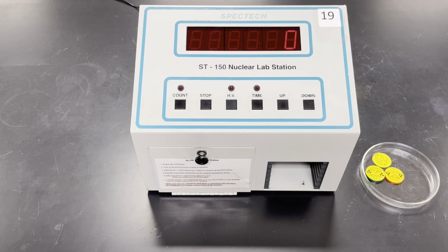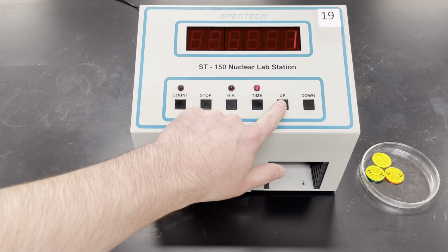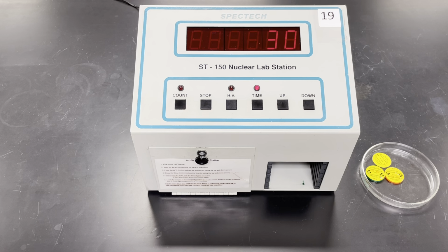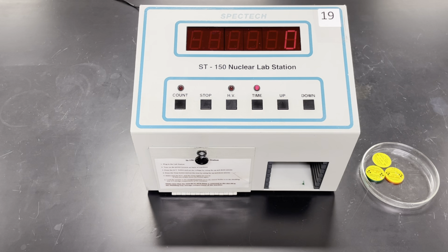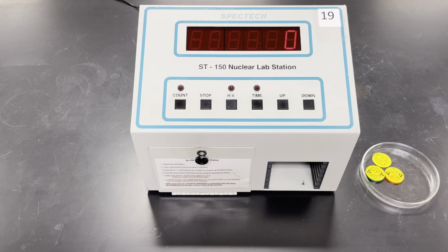Now, in order for us to collect radiation, rather than just turning it on like the little handheld Geiger counter, this one we set on a timer, and it will continue to count radiation as long as that timer is going. To set our timer, we press this button that says time, and we're going to up it to, let's say, 30 seconds. So half a minute, right there. Now, to say that I'm done selecting the time, I hit this button here. Now this is showing that our timer is on 0 seconds out of the 30 seconds, and it hasn't started going yet. So I need to hit the button one more time, so I'm fully back to the start.